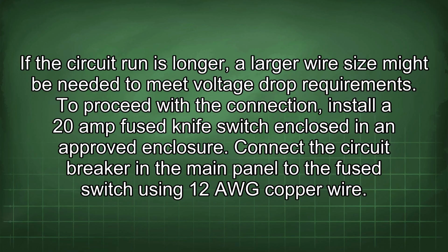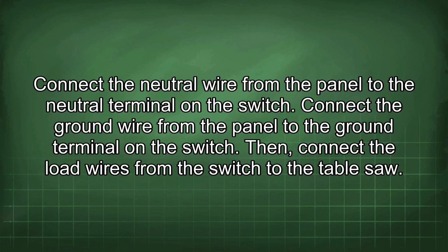To proceed with the connection, install a 20 amp fuse knife switch enclosed in an approved enclosure. Connect the circuit breaker in the main panel to the fused switch using 12 AWG copper wire. Connect the neutral wire from the panel to the neutral terminal on the switch. Connect the ground wire from the panel to the ground terminal on the switch. Then connect the load wires from the switch to the table saw.